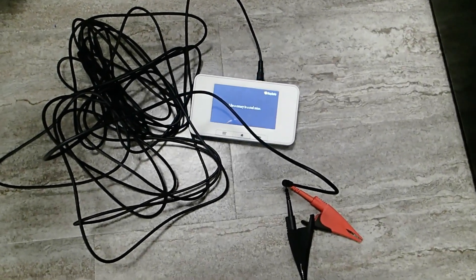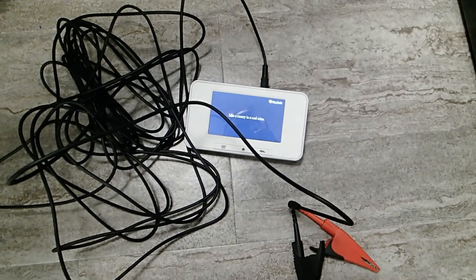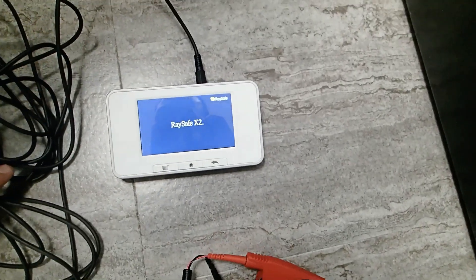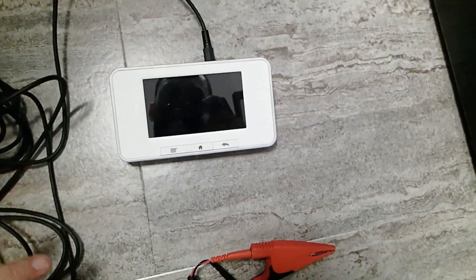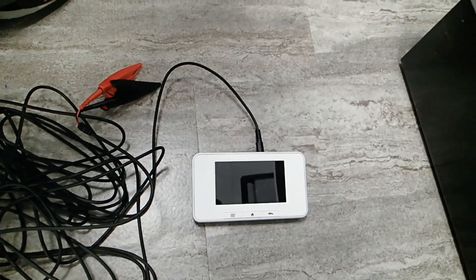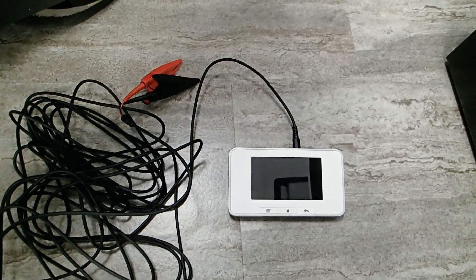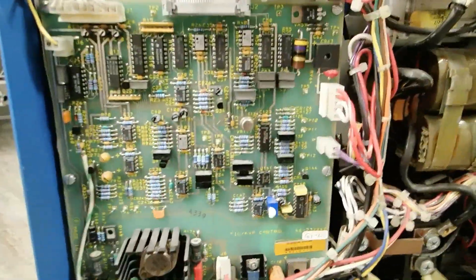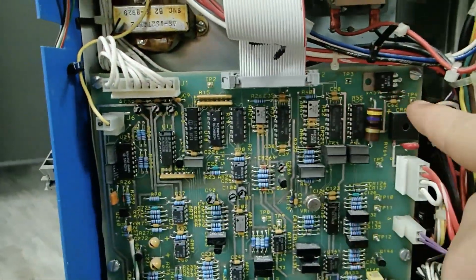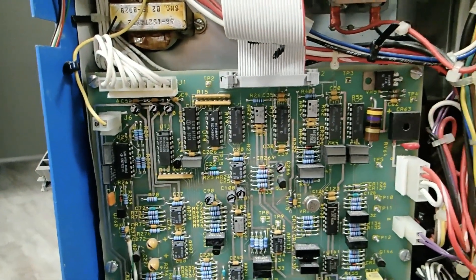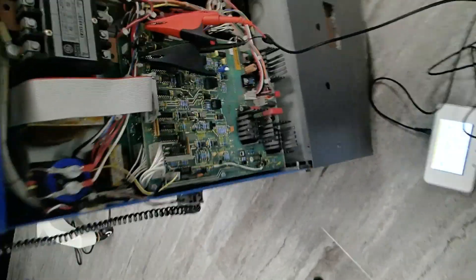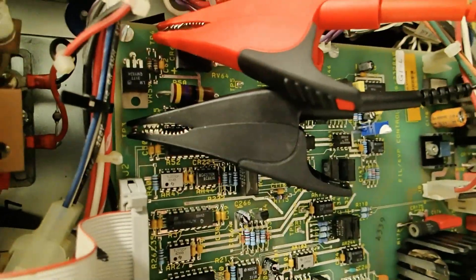To do the mAs test, we're going to be using the RaySafe. I have my RaySafe main unit here, then I have the cable to measure MAS. I have two alligator clips I'm going to use to connect to TP3 and 4. You want to connect to test point 3 first on the board. TP3 is right there. Test point 4 is right over here. We've gone ahead and installed the meter. Everything's set up, connected to TP3 and 4.